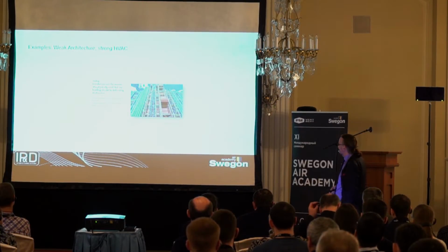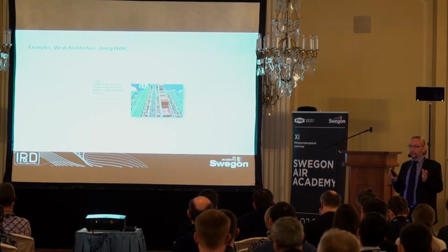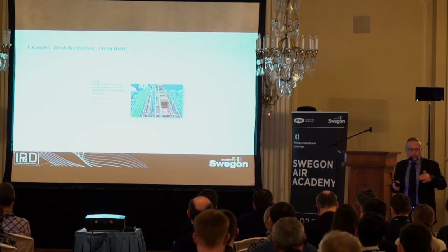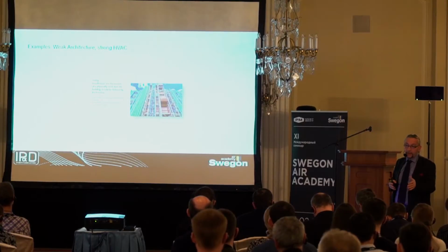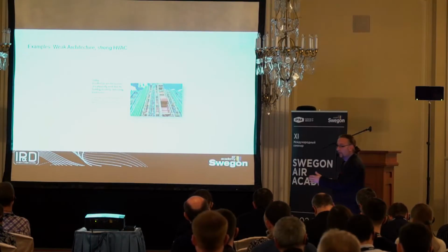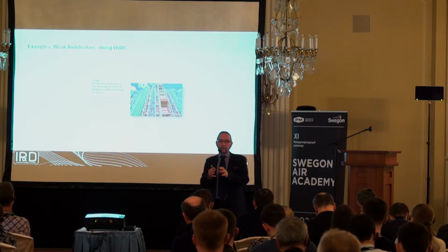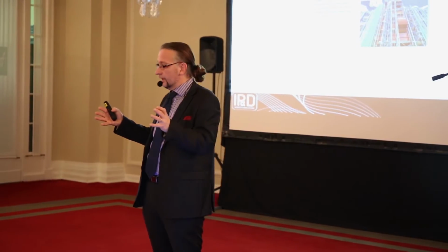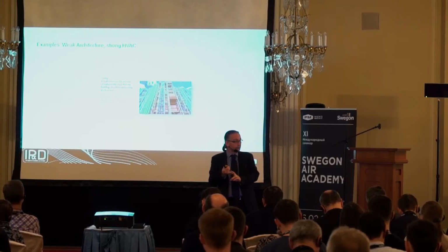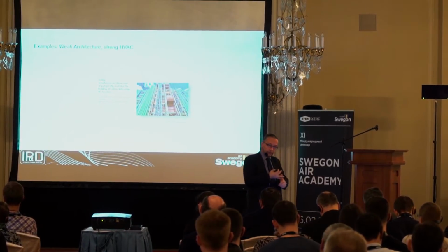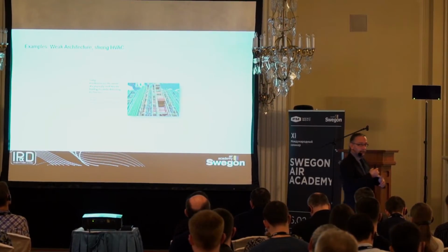It's important to understand that the typical installation space inside a building is related to the building type. For example, in a retail building, like a shop, you need to allocate about 8% of the floor space for installations. In an office building, it's 9 to 11%. In a hotel, it's about 17%. If you don't respect these numbers, either your space will be too big and you'll lose rentable square meters, or if you make it smaller, you'll have no room for pipe work, duct work, maintenance access, or efficient machines with good SFP, COP, and EER.